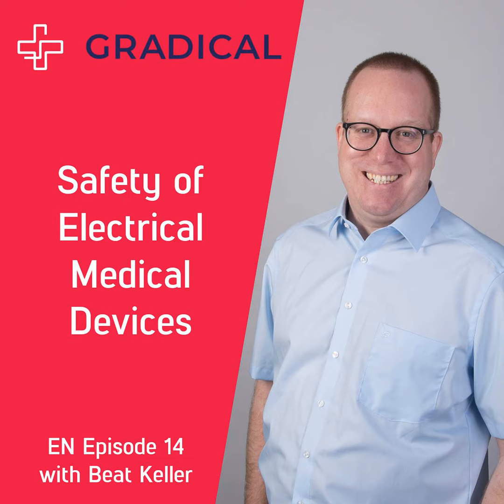And this is something you need to check while your device is on the shaker and see whether it still works. Yeah, and would that then be a requirement, or can you just state, yeah, this device cannot do it under these conditions, so please don't use it on a helicopter? So it is the intended use definition of your device.